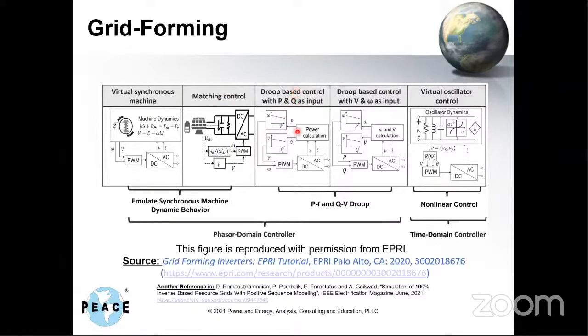Then you have this droop-based control, where you're again controlling that phasor, but you're doing so through a droop of active and reactive power to tightly control voltage and power. And the droop-based control can go two ways. It can use P and Q as an input, or V and speed or frequency as an input. Then you have this virtual oscillator, where you have a virtual oscillator inside the controls, and you use that as your source frequency to control the converter.